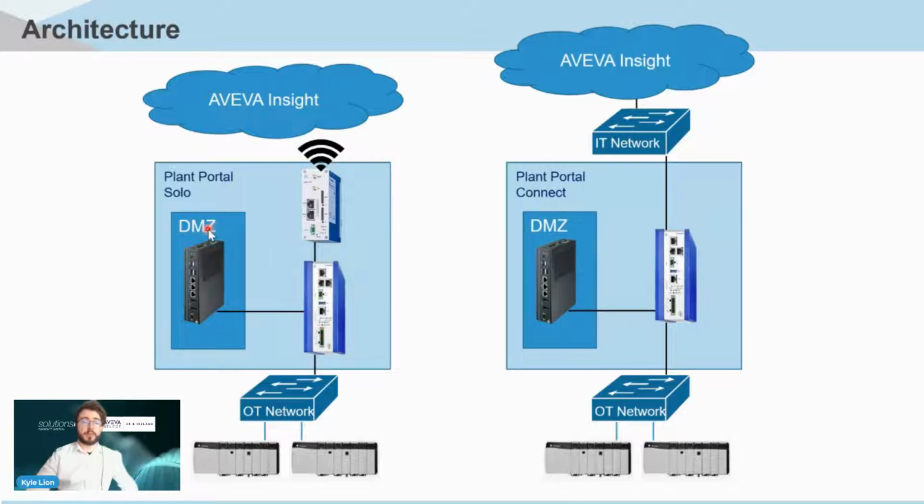And then in the middle of the DMZ, we have an Advantech IPC, and this is running our preferred choice of AVEVA Edge. This is our Edge gateway, and the reason why we chose AVEVA Edge is because it is edge-focused, cost-effective, and very much built to be deployed, portable, and scalable. The main features of it are that it has 250 plus built-in drivers for a variety of different devices and protocols, including OPC UA, MQTT, and SNMP, which will come up shortly.